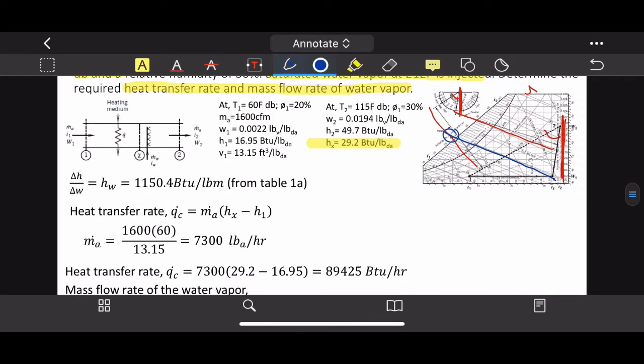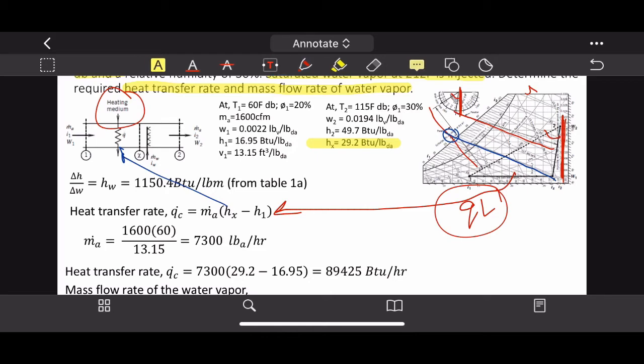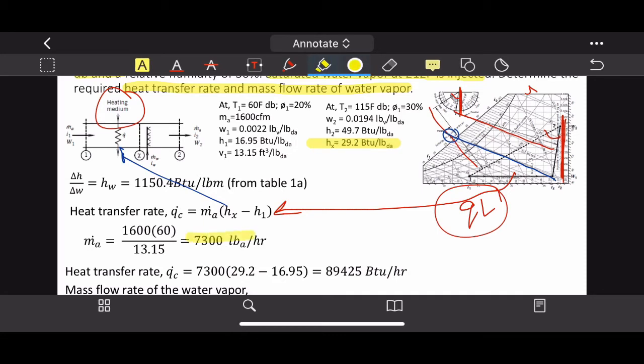The heat transfer rate for the heater only: qc = ṁa(hx − h1), with no water term because the heating medium section adds no moisture — it is purely sensible heat, temperature increase only. From this, ṁa = 7,300 lb of air per hour (converting from CFM to lb/hr). The heat transfer rate Q = 89,425 BTU/hr.